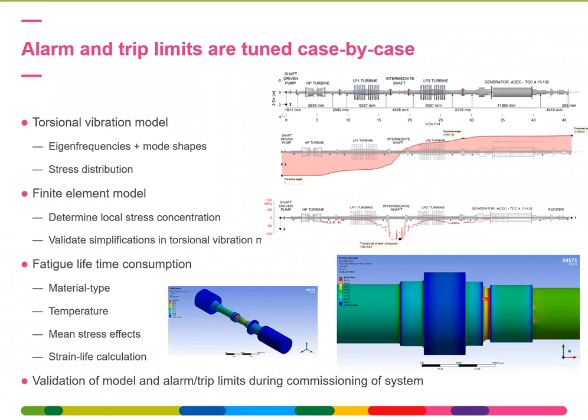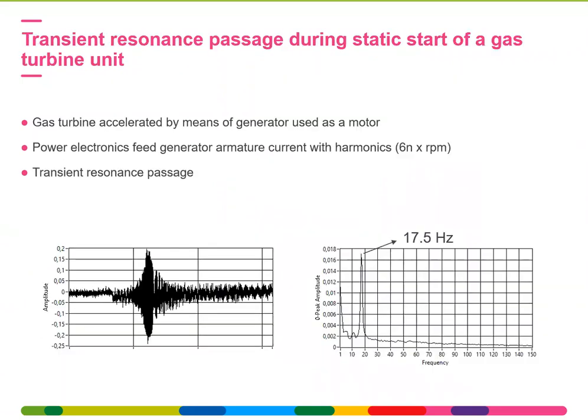It's tuned case by case, so every shaft line has different alarm and trip limits depending on the material and the type of shaft line. So this is really done case by case. Some examples. We've now covered the torsional system, so what is important is that it is tuned on your system. There's no general torsional vibration measurement system. It has to be tuned. Details on the shaft line have to be available: geometry, material, and if not available, some parts can be measured on site as well.